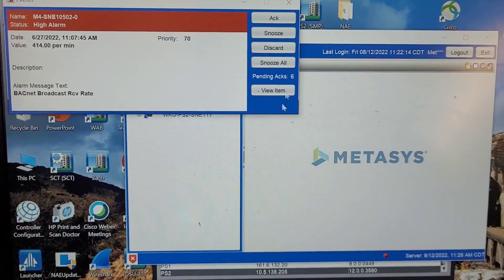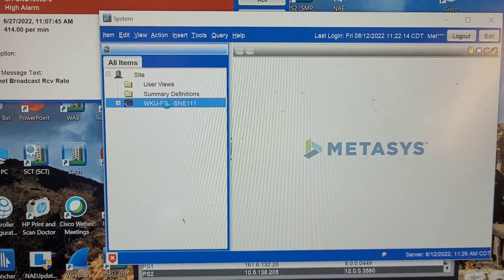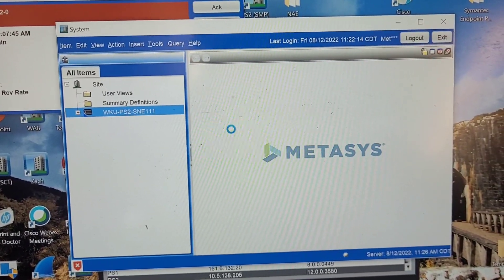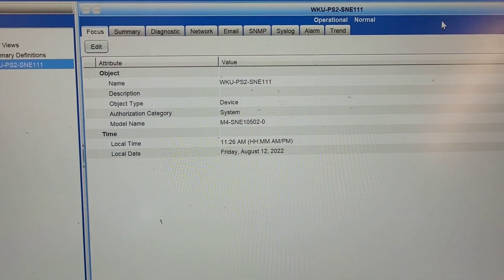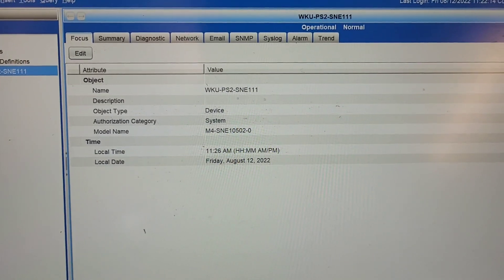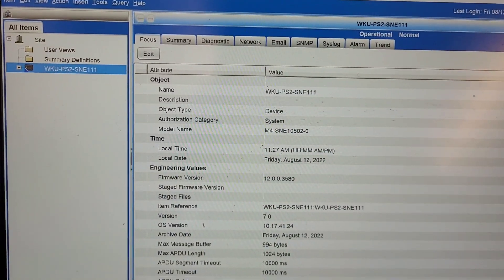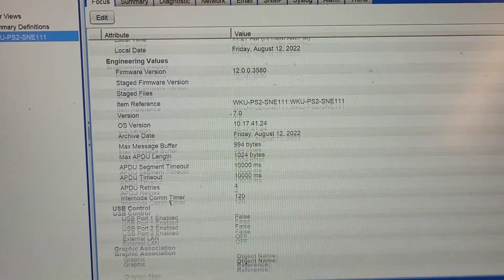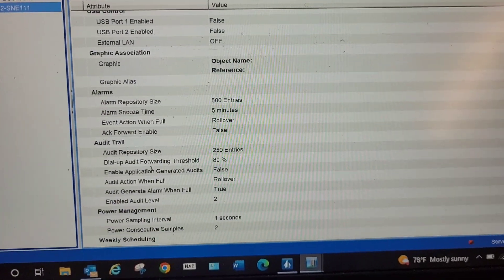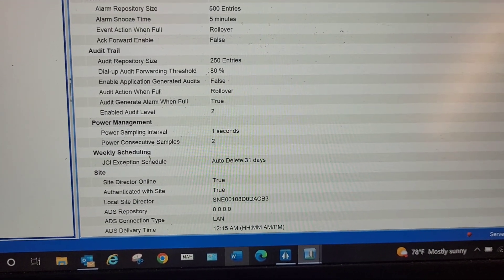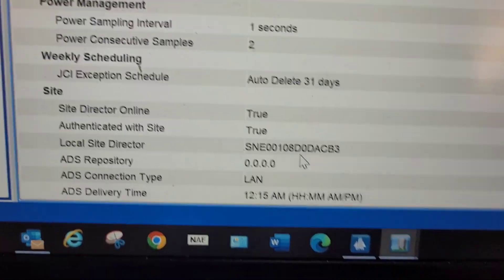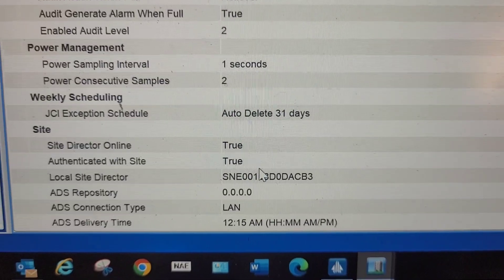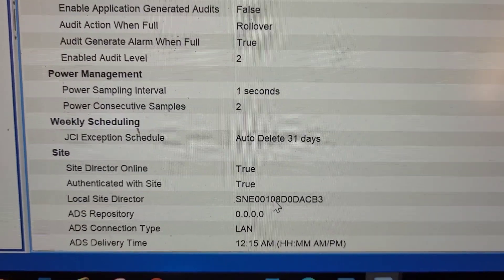If you guys remember from my previous videos, you'll know that one thing you have to do with an SNE is you have to demote it when you pair it with the server. So what you do, of course, what I've done on this one, I've already renamed it to the name that I want it to be. And under the focus tab, I have now browsed back into the engine. And now under the focus tab for the site director and repository, I have to enter the information for those. You can see currently that the local site director, that this engine sees itself as the site director. That is going to change.